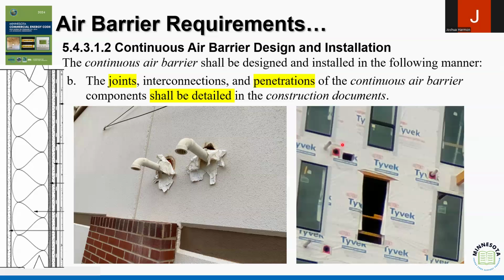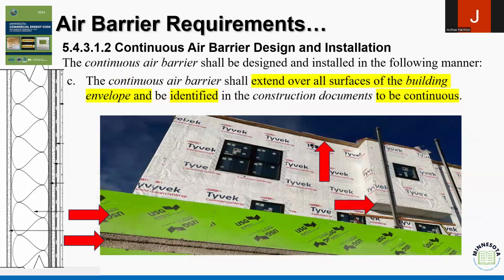What do we do if we have penetrations that are complete holes, right? Do we need to refill or rebrace this area before? Or do we just put a piece of plastic over this hole, a piece of poly over it, we're done? Or do we tape it, we're done? Do we run the 5 inches of caulk across it and that's good enough? Or do we want to reinstall a piece of sheathing behind it, or something that has structural static pressure resistance, right? Again, that's going to be an evaluation that we do as building inspectors and as planning examiners, thinking about how these buildings might be built on site.